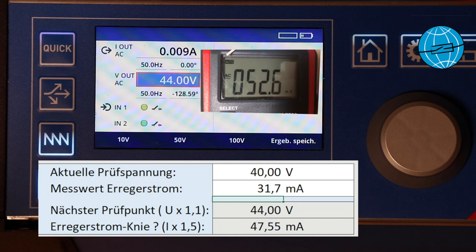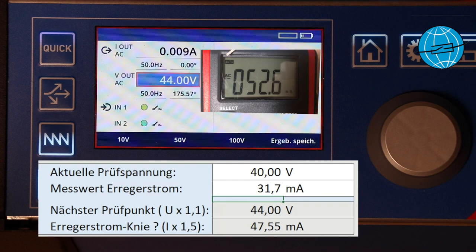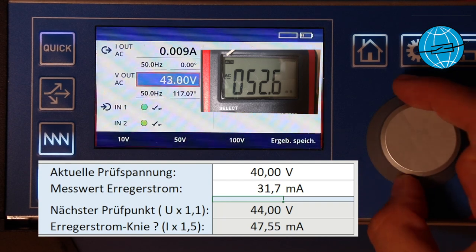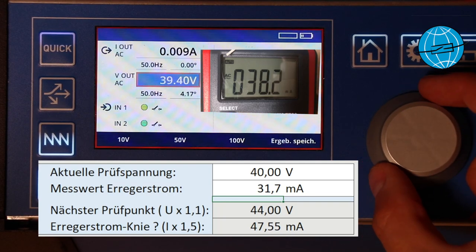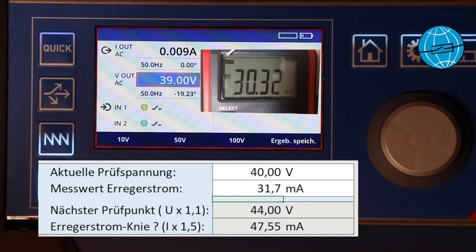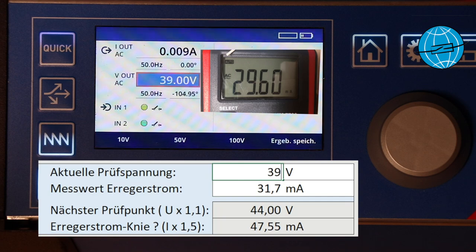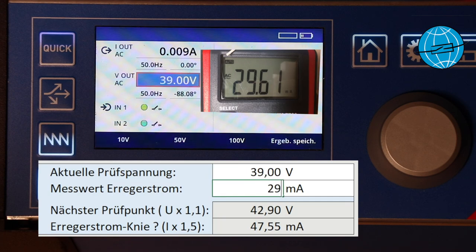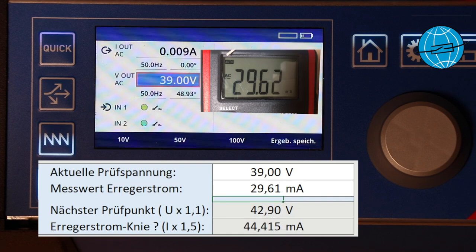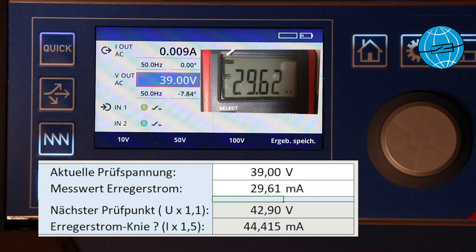Wow, the current jumps up to over 52 milliamps and we were searching for our value about 47.5 milliamps which means we are already too high and we have to go back a little. Since the 40 volts are already above the knee point voltage, let's go back to 39 volts and we will see what happens.